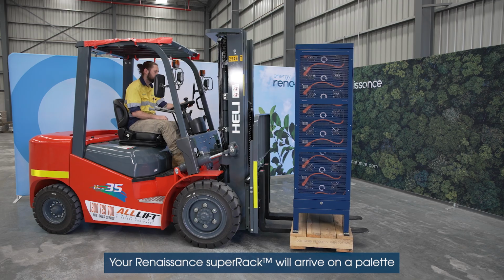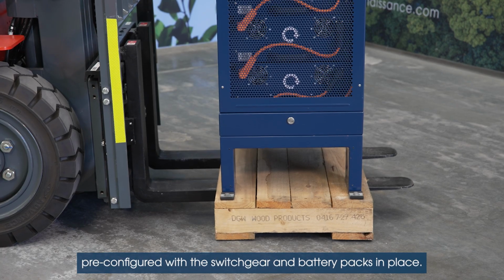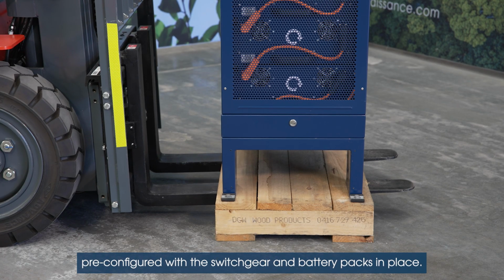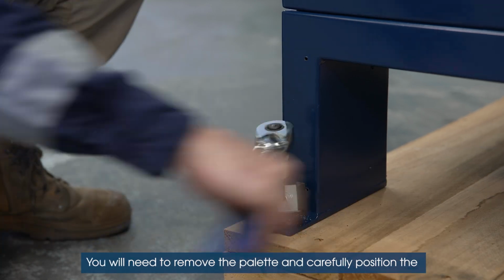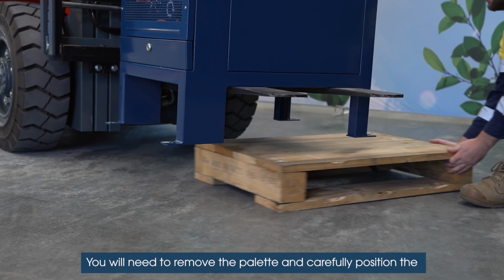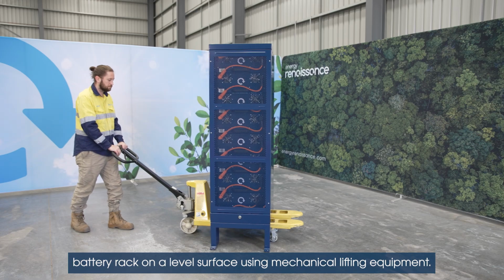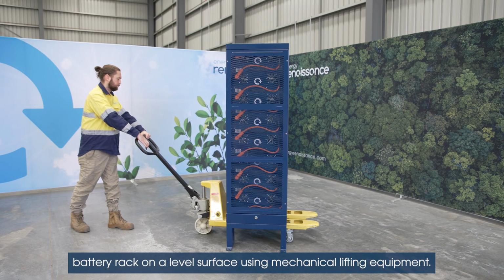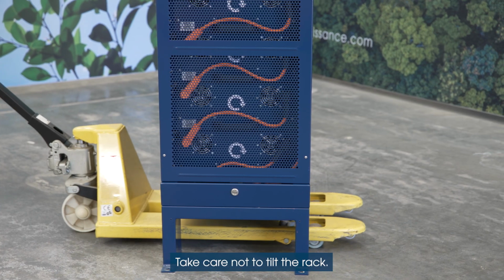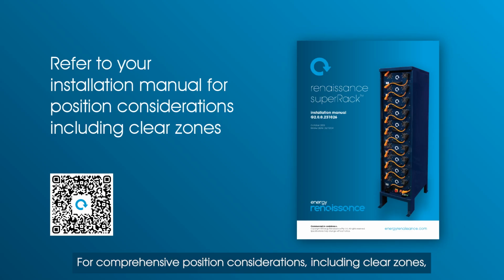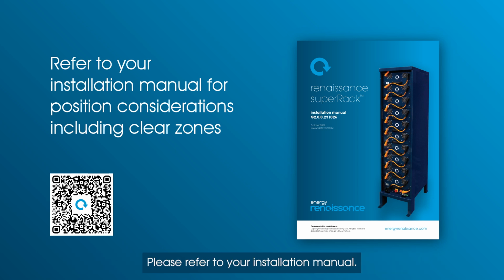Your Renaissance superRack will arrive on a pallet pre-configured with the switchgear and battery packs in place. You will need to remove the pallet and carefully position the battery rack on a level surface using mechanical lifting equipment. Take care not to tilt the rack. For comprehensive position considerations, including clear zones, please refer to your installation manual.